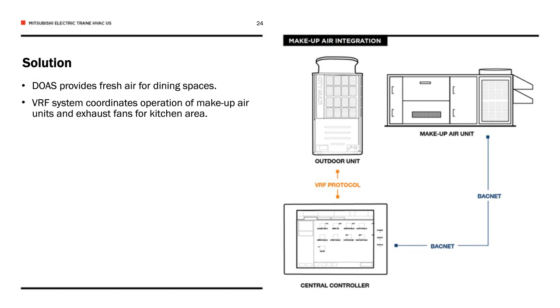A third-party mechanical ventilation system that natively uses a different proprietary protocol and controls can be integrated with a VRF system through a simple input-output configuration. The same input-output configuration is used for a third-party DOAS that could then coordinate the operation of makeup air units and exhaust fans.